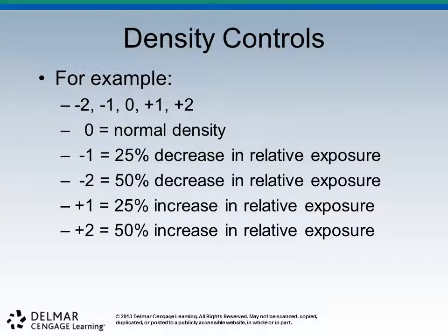And if we do that, we're going to increase our density amount by about 25%, or that's going to be the exposure, which should increase our density. But that all depends on the patient, of course. That's sort of out of our control. So when you leave it at 0, it's expecting the normal configuration, normal programming, normal amount of exposure. If you, for whatever reason, go up to +1, it's going to say, well, then I need to increase that.